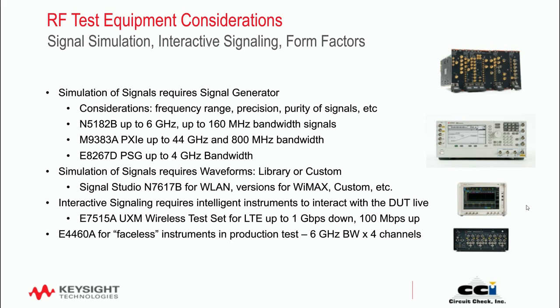At the most severe end, which we didn't discuss a great deal, you may need interactive signaling to act as if you had live interference going on. If you don't actually use a router and a wireless device as your unintended signal, you may need intelligent instruments to generate simulated communications in a very controlled way. Some of these, such as the UXM wireless test set, can do that.